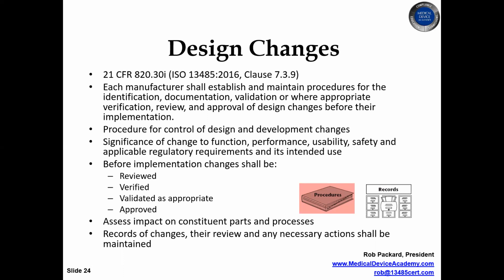I just had a company in the last 24 hours ask me, do we need to submit a new 510K for adding UDI labeling to our product? No, you don't. UDI is not something that's considered a significant change. Yes, it's a change, so you would document it and you'd update your labeling, but you're not going to submit a 510K for that.